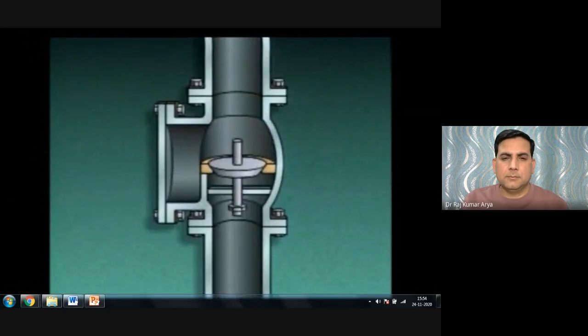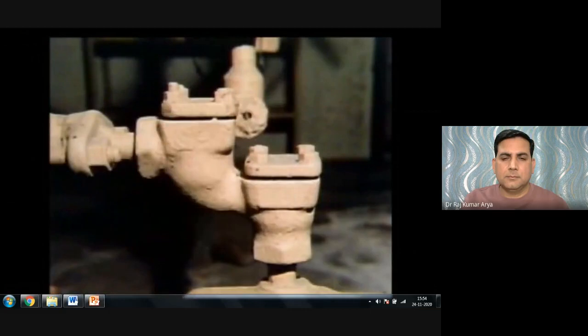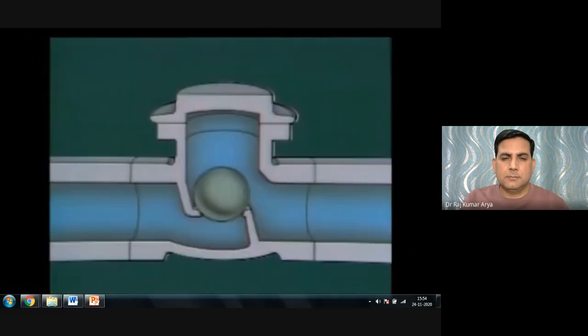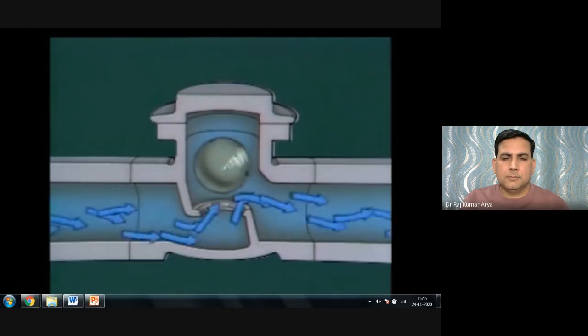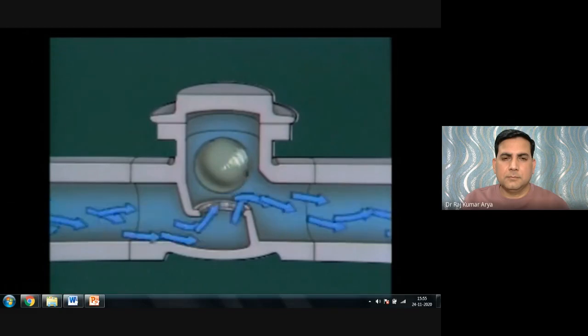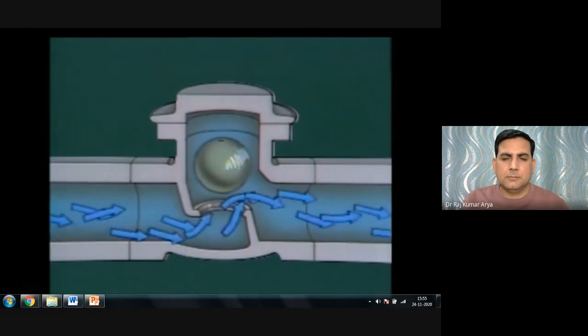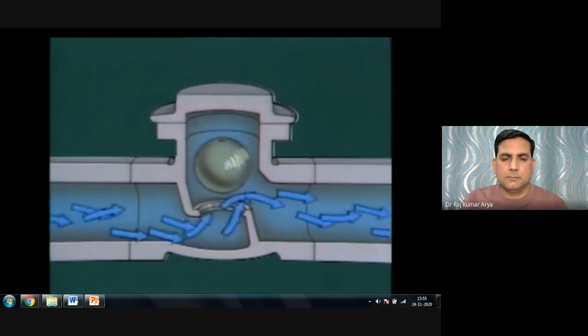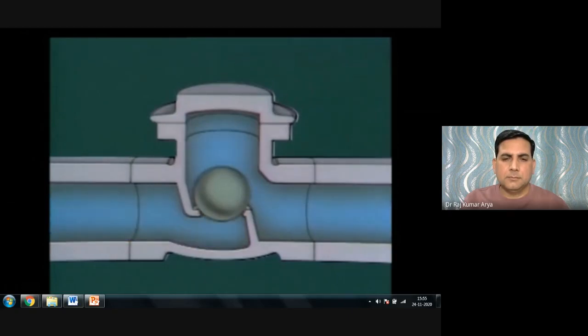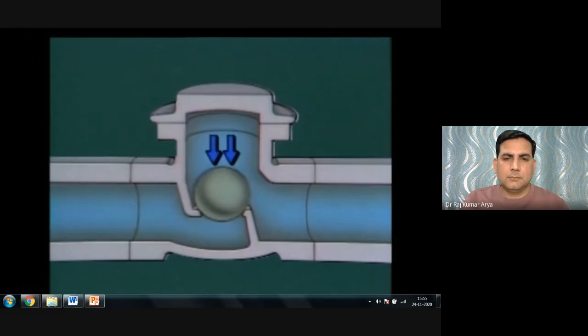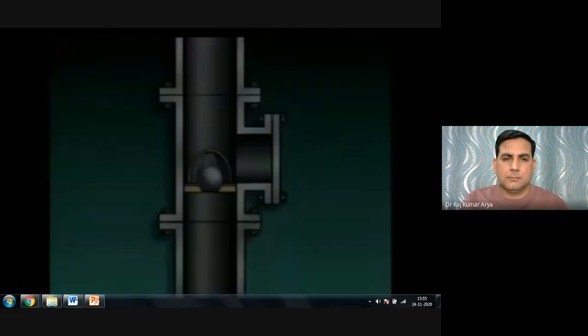A ball check valve consists of a valve body, a seat, and a ball. When fluid flows, the ball is pushed out of the seat and rotates in the fluid flow. Since it is difficult for solid materials to stick to the spinning ball, these valves are useful for handling liquids containing scale and sediment. When flow stops, gravity pulls the ball onto the seat and backflow holds the ball firmly in place. Like the lift check valve, the ball check valve can be used in horizontal or vertical positions.